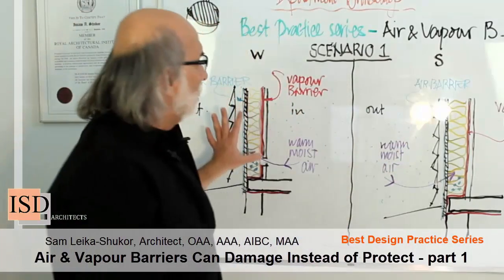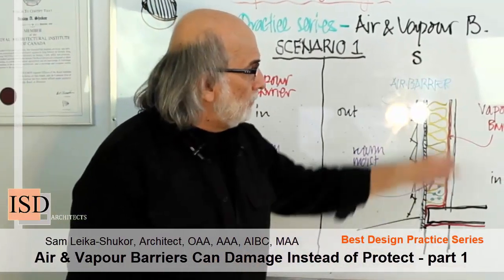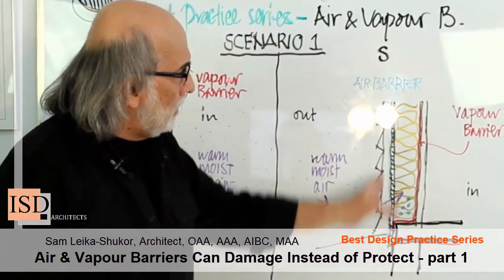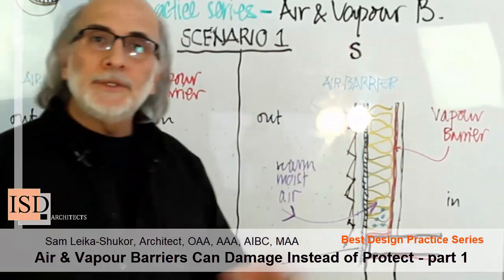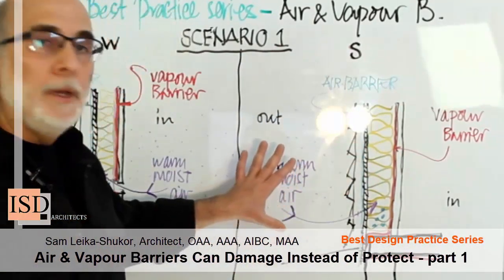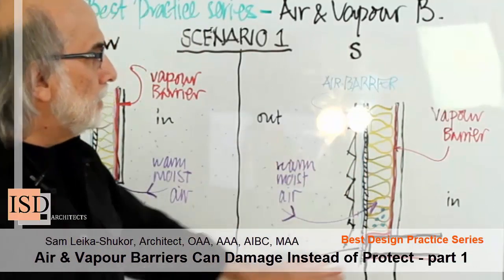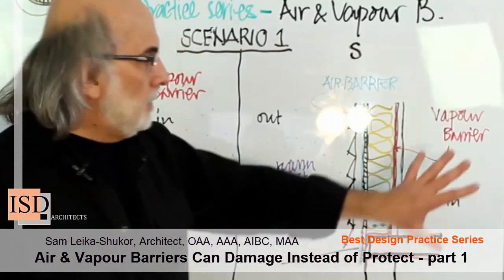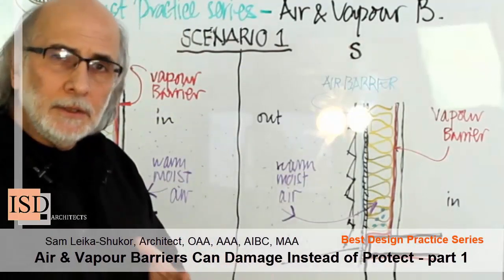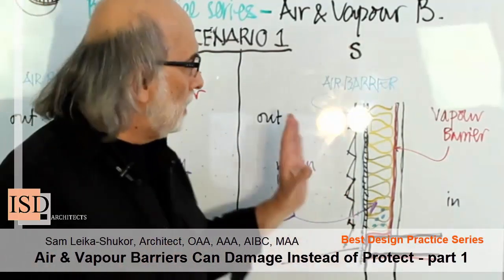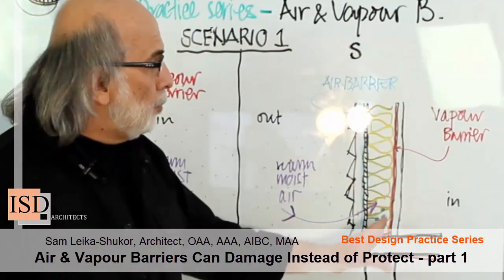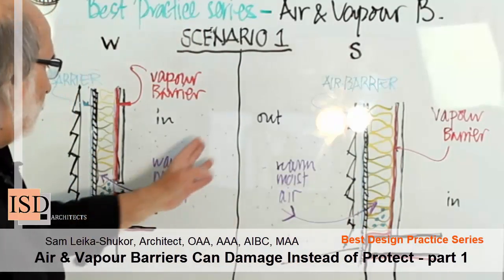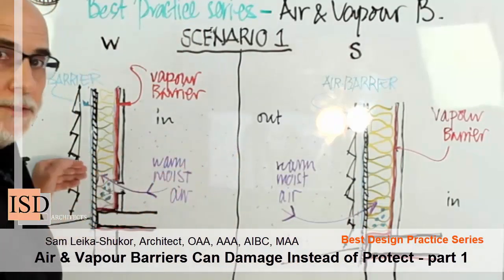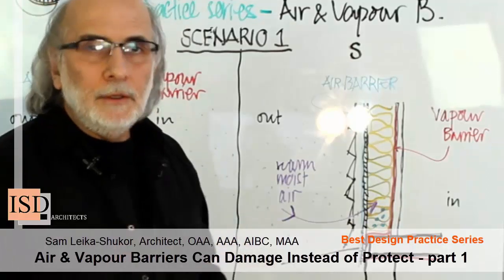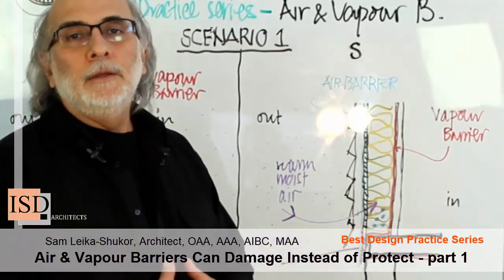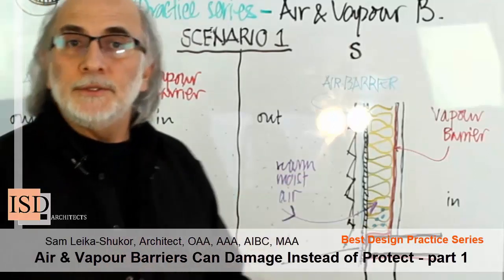What about the same wall in the summer season? Well, the vapor barrier is in the same location. The air barrier is in the same location. In the summertime, the situation is reversed. So the warm and humid area is outside, while the colder area is actually inside, either by the use of air conditioning or just by the fact that there is a temperature differential. And that is exactly the opposite of the winter scenario, where the air moves from the more moist into the drier. So over the years, this area becomes soft, and it will impact the structural integrity of the building.